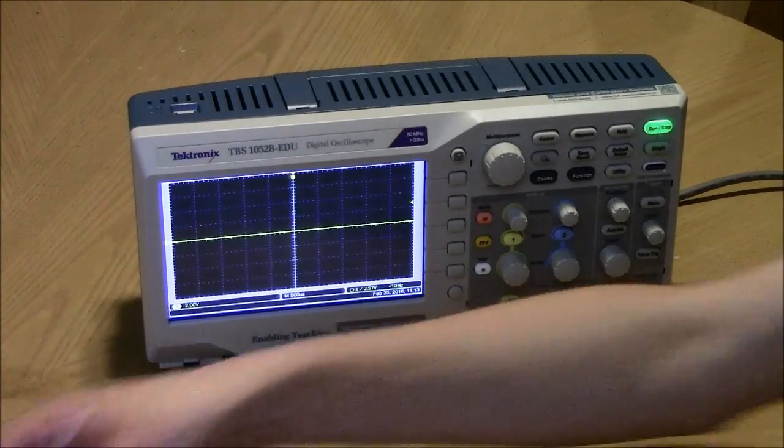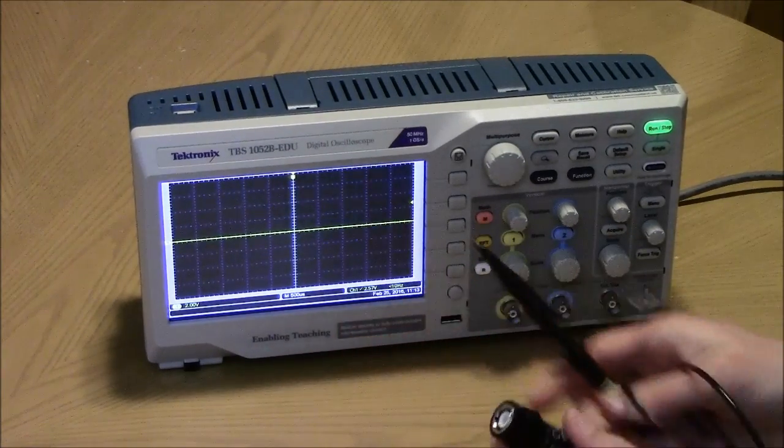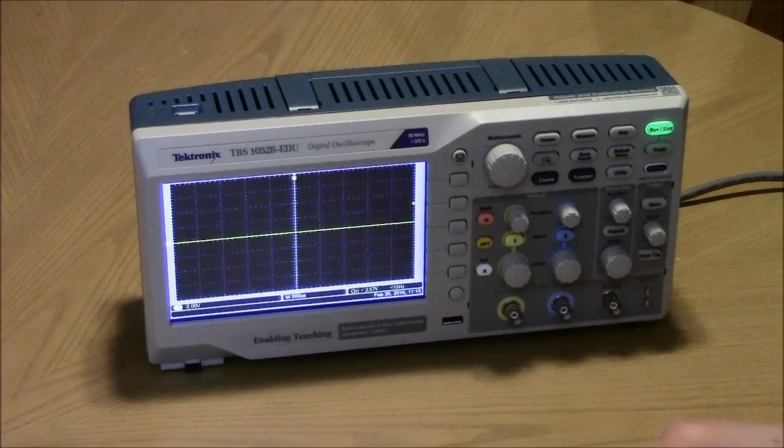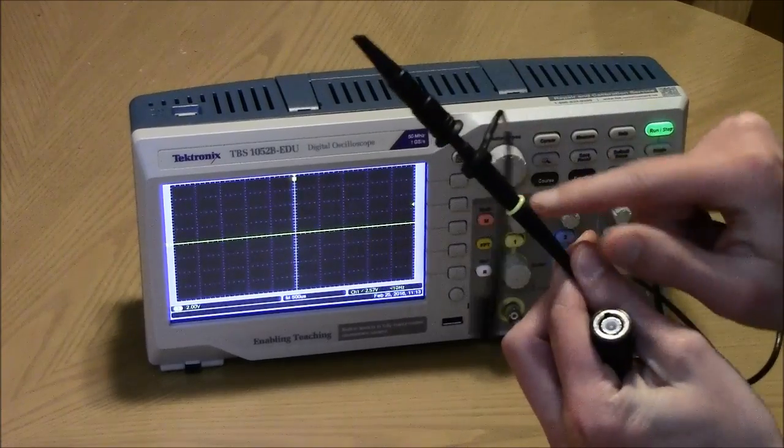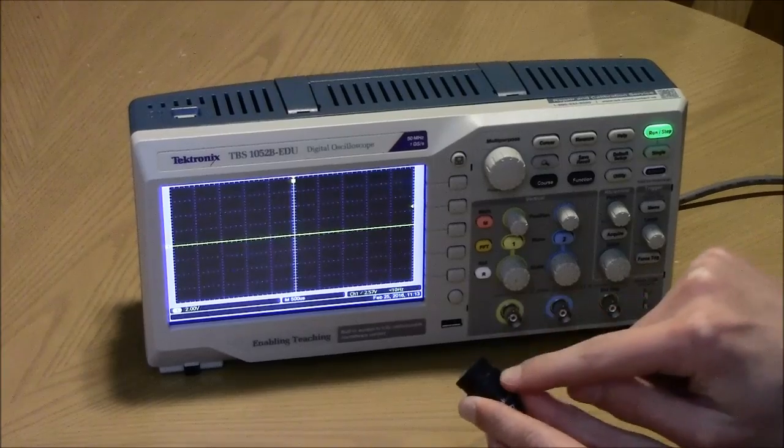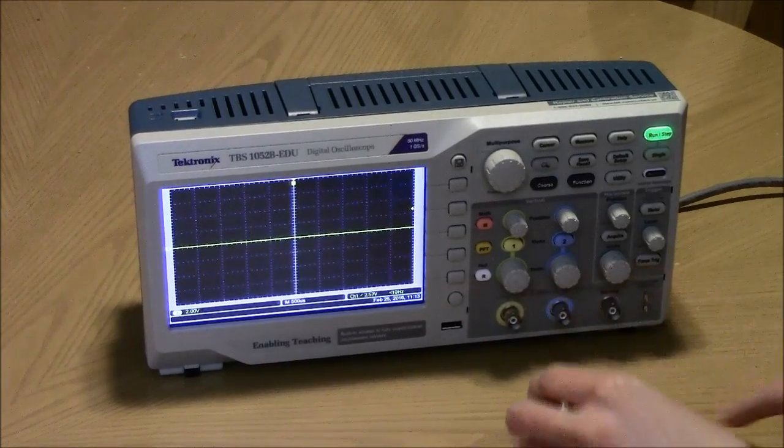The first thing you want to do is connect a probe. They go in these two ports here, this yellow one and blue port here. We've got the yellow ring flag on this one so we'll put it in the yellow port. To put it in you'll line up these little ridges with the ridges on the port.